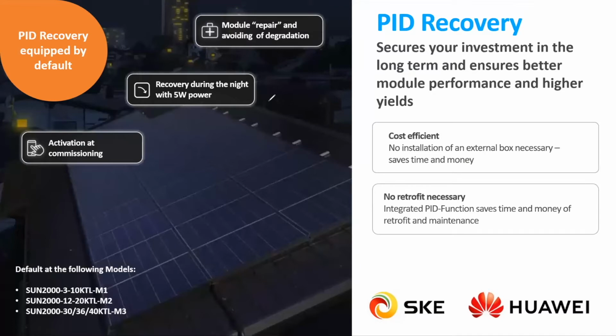Most of our inverters in the commercial range are equipped with a potential induced degradation recovery module. This has the benefit of preventing this effect from happening and also healing the PV modules. In time, the modules will lose efficiency because of this effect. But by having this module, which works during the nighttime and consumes only 5 watts of power, you can prevent this from happening, and you will have great benefit during the lifetime of the PV plant.